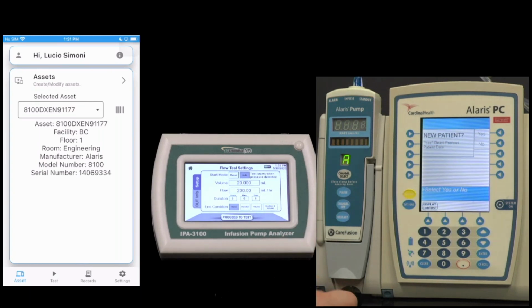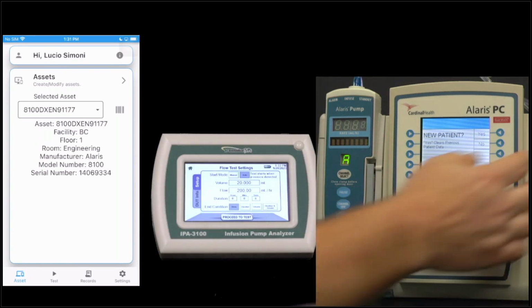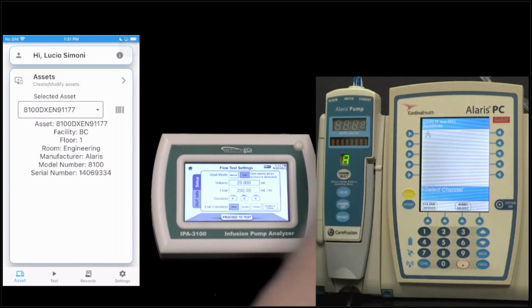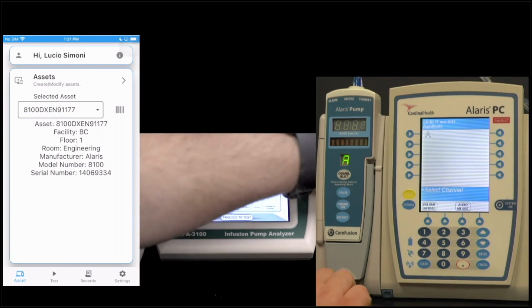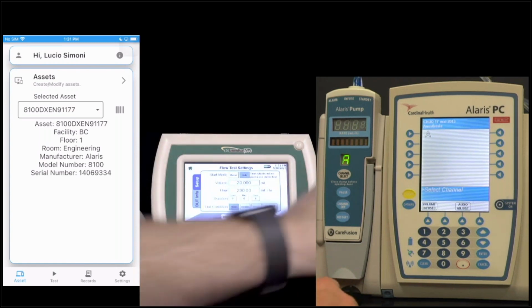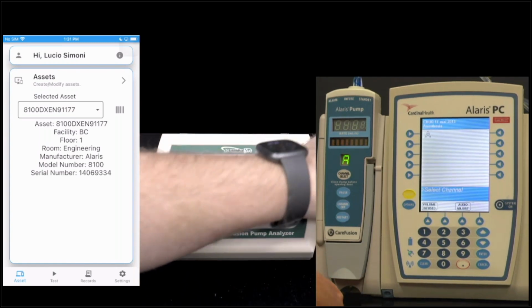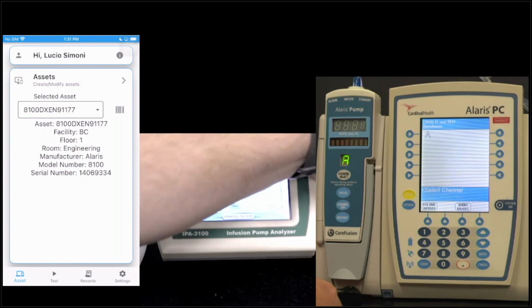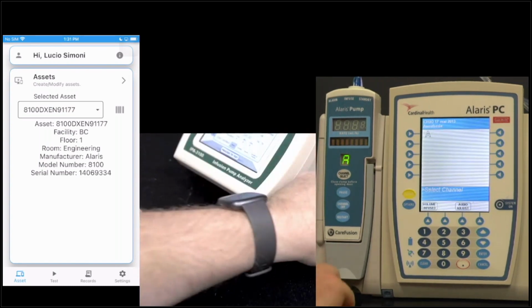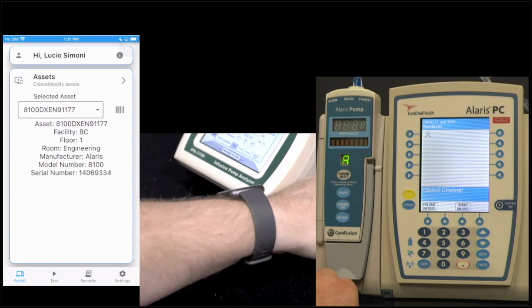But sometimes you get bubbles trapped on the outlet side, the patient end of the tubing, and they get clear and then go through the equipment. So we can ignore those bubbles, and I'm going to demonstrate that here. I brought my fittings, so I'm going to put in a T after the infusion pump. Again, we don't want the pump to have an alarm. But what happens if you thought you cleared your tubing and just a stray bubble comes running through? What's that going to do to your test?